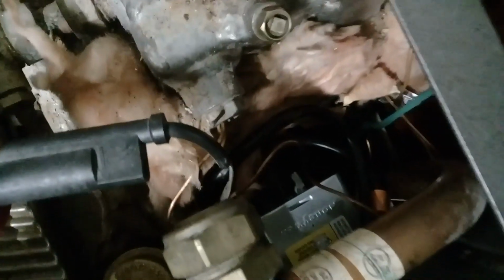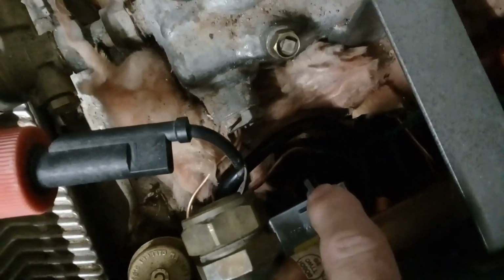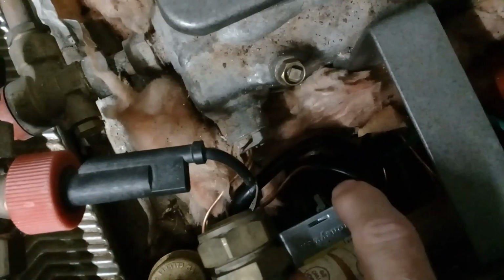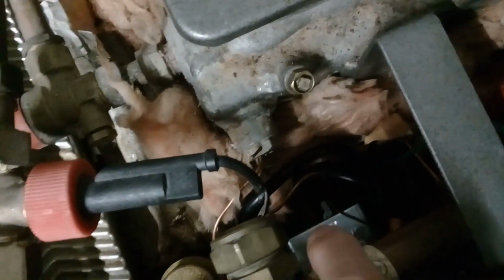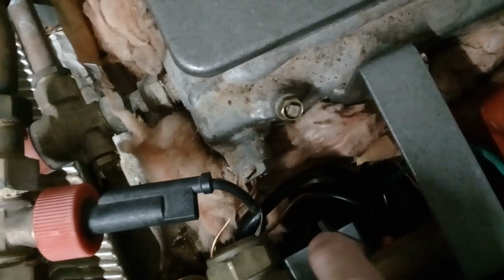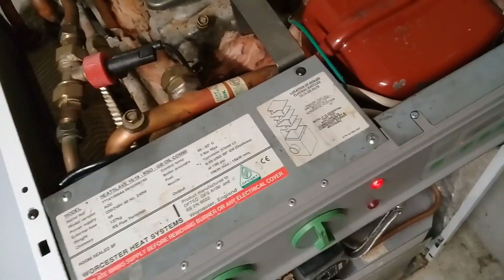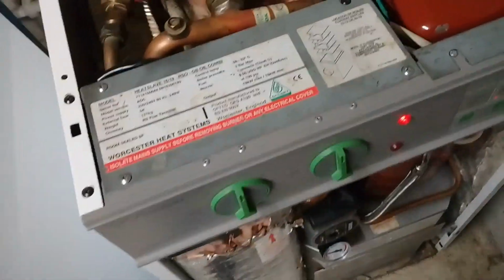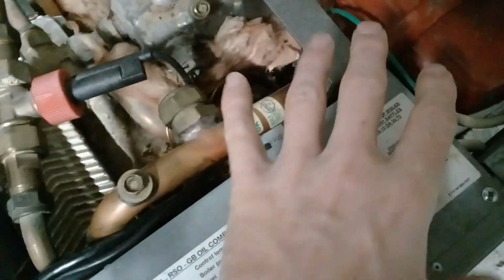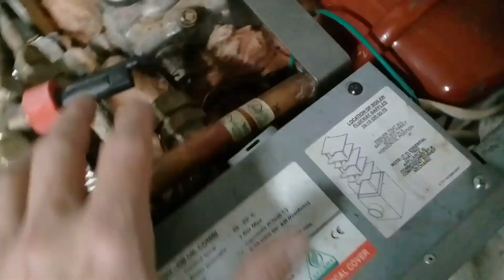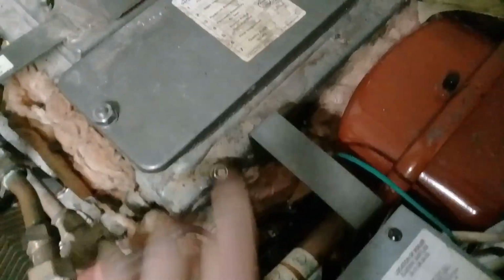One thing to bear in mind, the three-way valve down there, what you want to do is move it to the left where it hooks in, so it's between heating and central heating. Put the boiler on the hot water setting, so just make it call for hot water, and that way the air bubbles or any air in the system will rise from the heat store and also from the system, and then you can just bleed the air out from here.